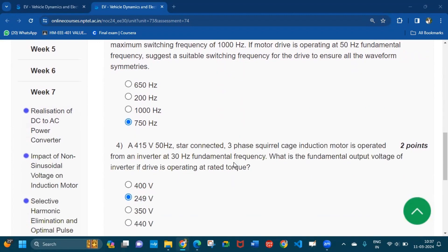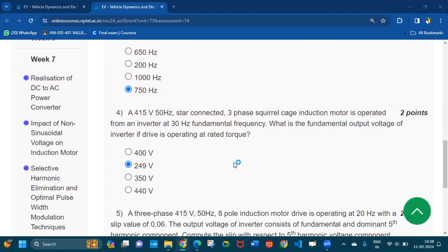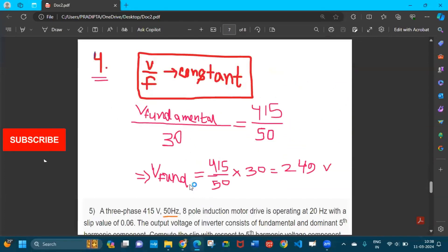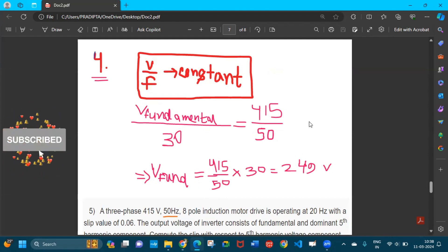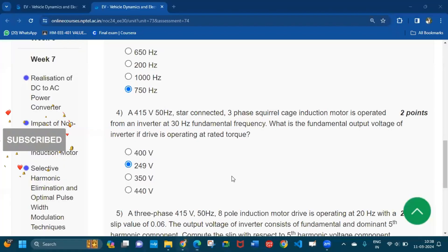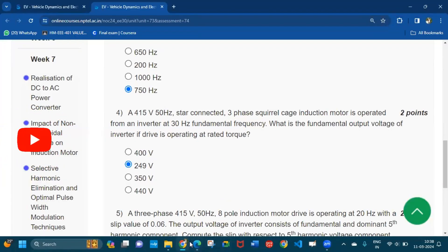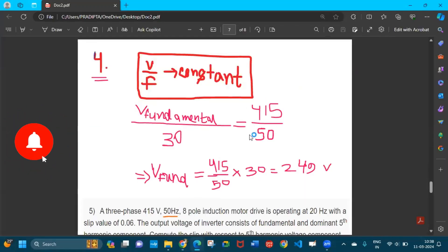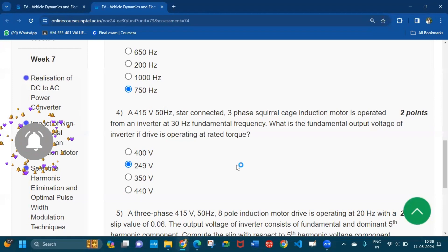Question number four: a 415 volt, 50 hertz, star-connected three-phase squirrel cage induction motor is operated from an inverter at 30 hertz fundamental frequency. What is the fundamental output voltage of the inverter if the drive is operating at rated torque? For this, V/f is kept constant, so V_fundamental / 30 = 415 / 50. Solving: V_fundamental = 415 × 30 / 50 = 249 volts.